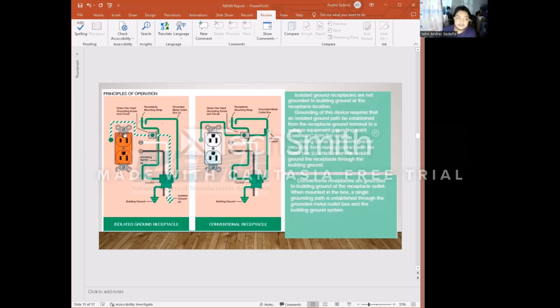Isolated ground receptacles are not grounded to the building ground at the receptacle location. Grounding of this device requires an isolated ground path established from the receptacle ground terminal to a suitable equipment grounding point upstream from the device. While conventional receptacles are grounded to a building ground at the receptacle outlet when mounted in the box. A single grounding path is established through the grounded metal outlet box and the building ground system.